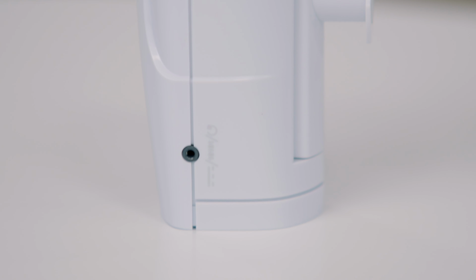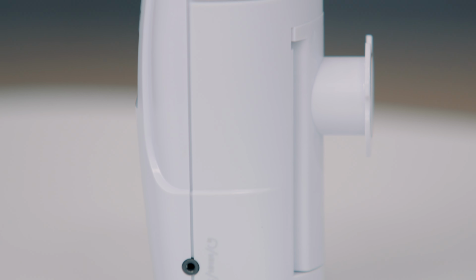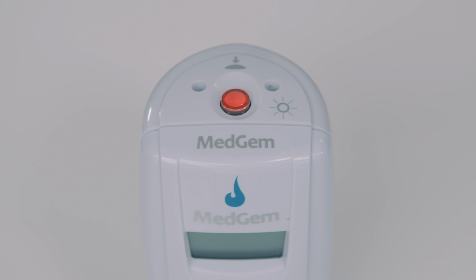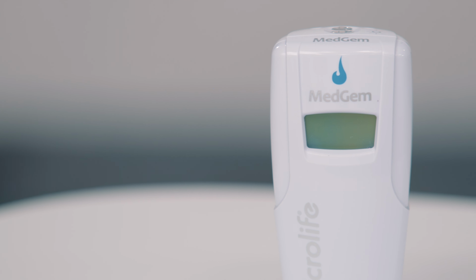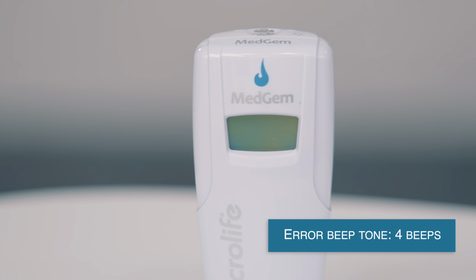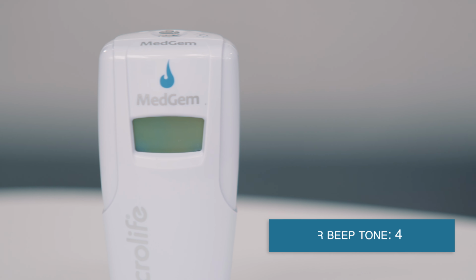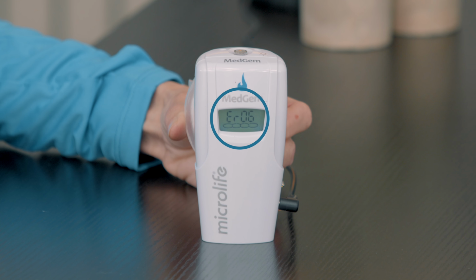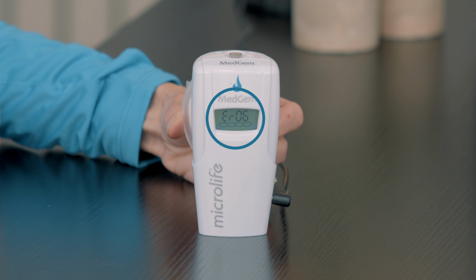If there is a problem with the MedGem device, the following will occur. The indicator light on the top of the MedGem device will turn red. An error beep tone of 4 low-frequency beeps will be heard. An error code will be displayed in the MedGem LCD window.